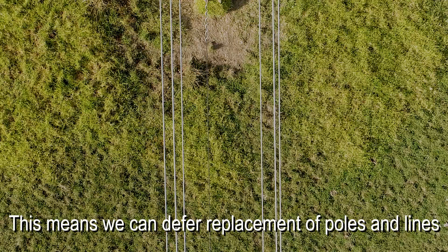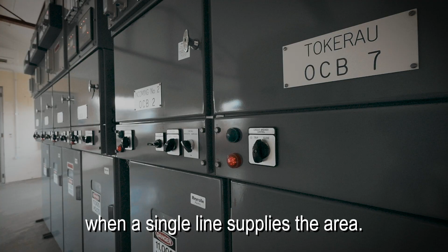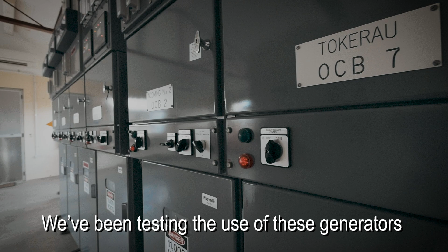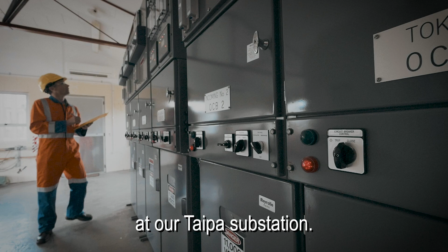Diesel generators offer a solution where we can maintain supply while working on planned and unplanned outages when a single line supplies the area. We've been testing the use of these generators since 2012, with 2 units installed at our Taipa substation. They've run to cover unplanned outages about 3 times a year, and about 13 times a year when we rebuilt the line into the area.